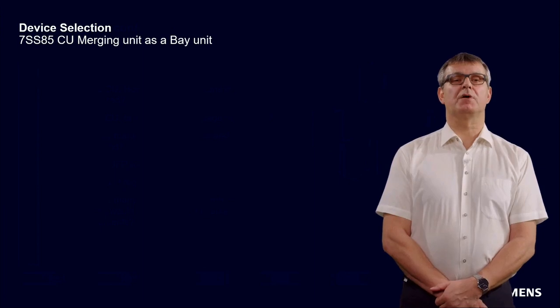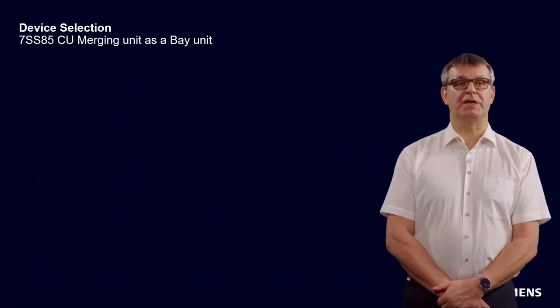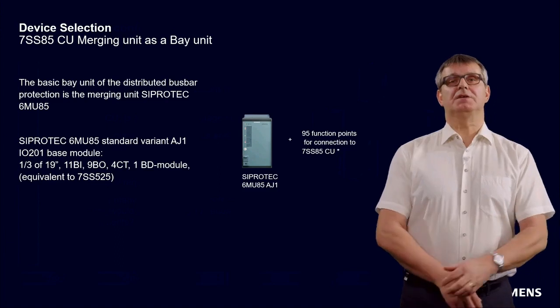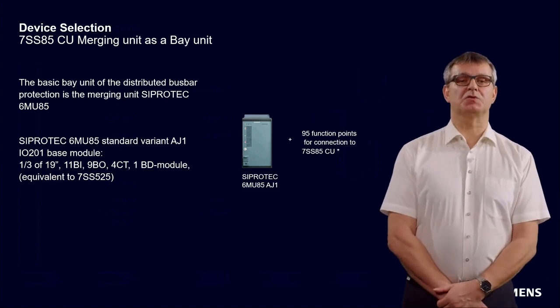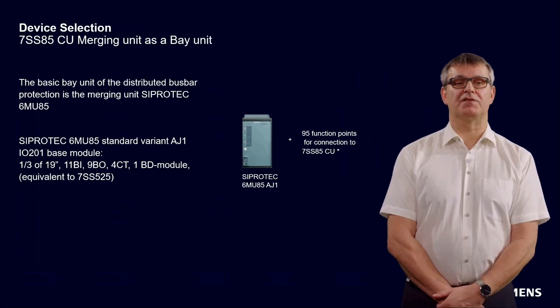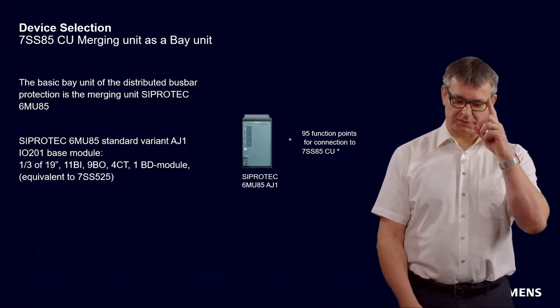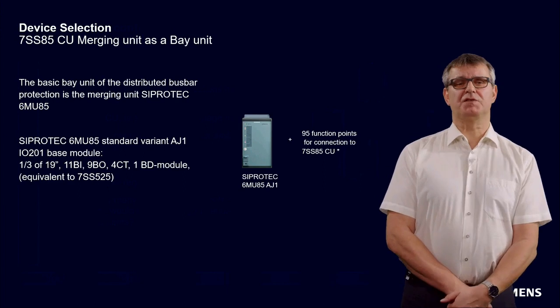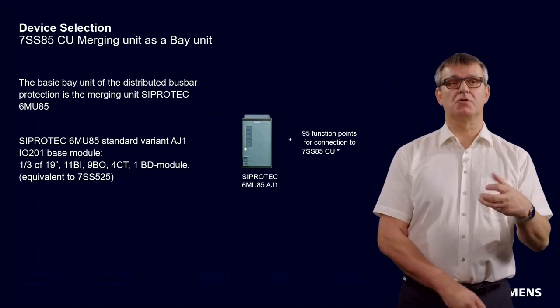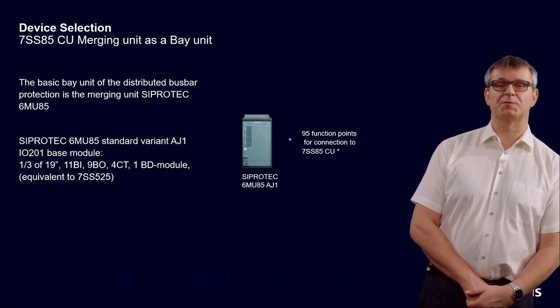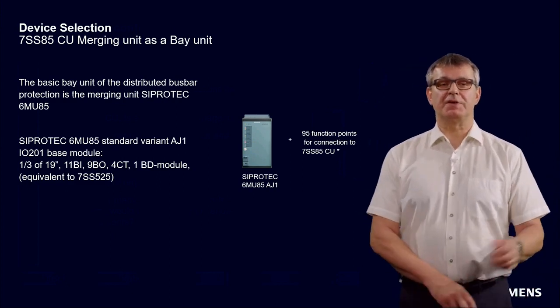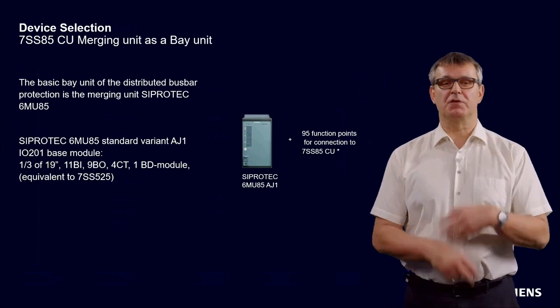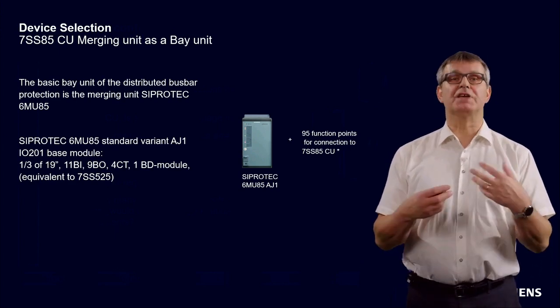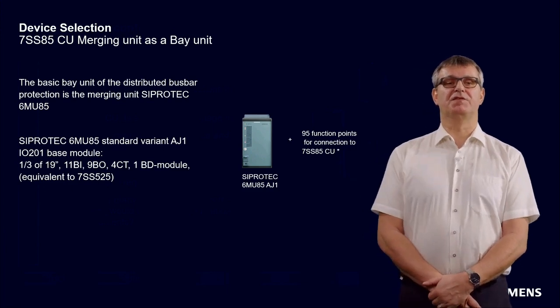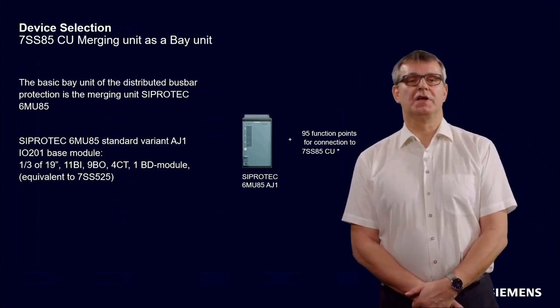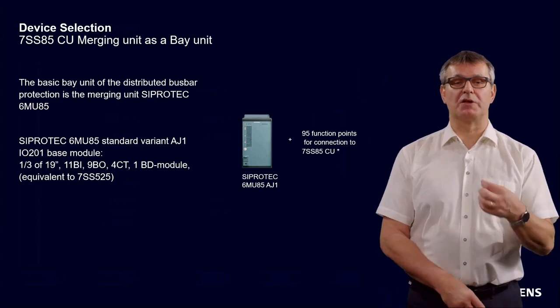Some words about finding the correct merging unit as a bay unit. The dedicated bay unit for the distributed busbar protection, in the first step, is the 6MU85. When I remember correctly, more than 50% of the audience already knows the 7SS52 busbar protection system quite well. To make it easier, if you are used to configuring a busbar protection system with a 7SS52, you can take the following approach.